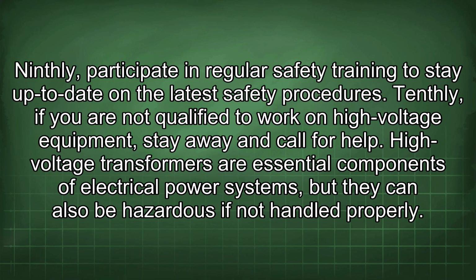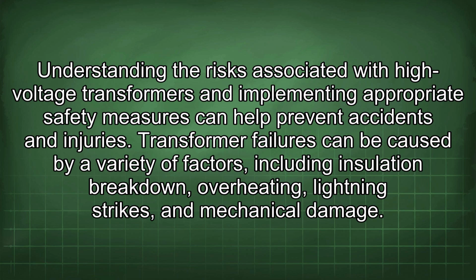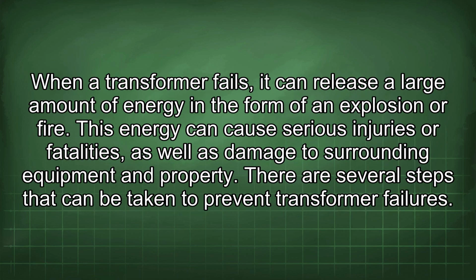High-voltage transformers are essential components of electrical power systems, but they can also be hazardous if not handled properly. Understanding the risks associated with high-voltage transformers and implementing appropriate safety measures can help prevent accidents and injuries. Transformer failures can be caused by a variety of factors, including insulation breakdown, overheating, lightning strikes, and mechanical damage. When a transformer fails, it can release a large amount of energy in the form of an explosion or fire. This energy can cause serious injuries or fatalities, as well as damage to surrounding equipment and property.